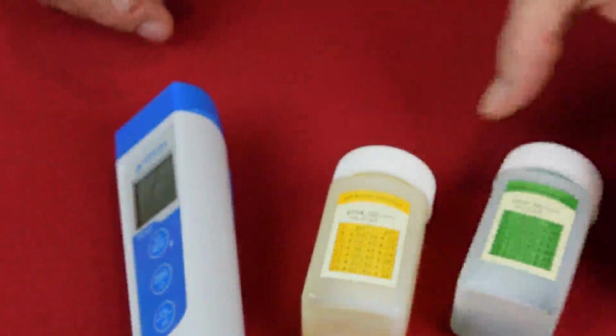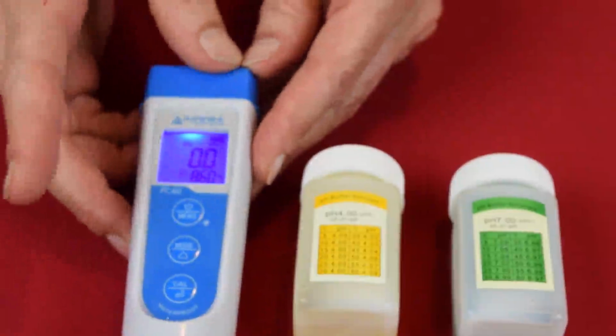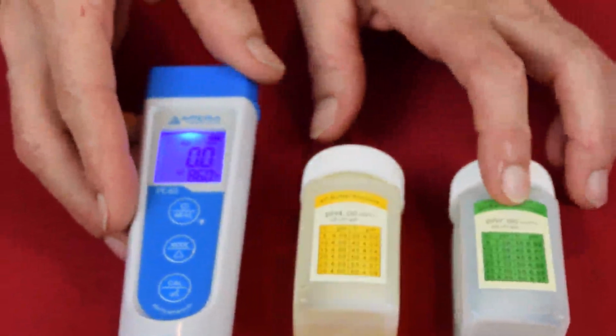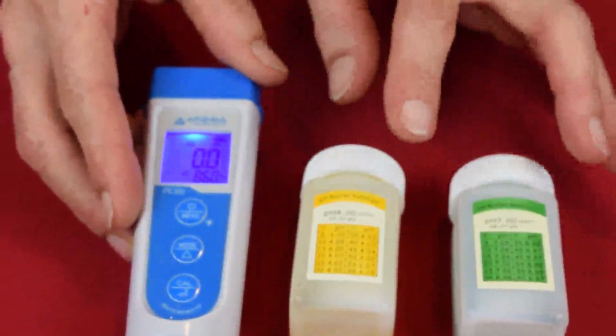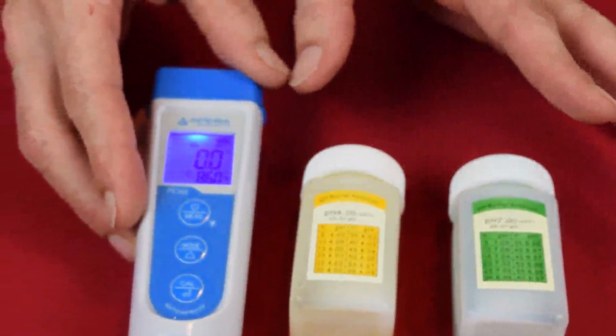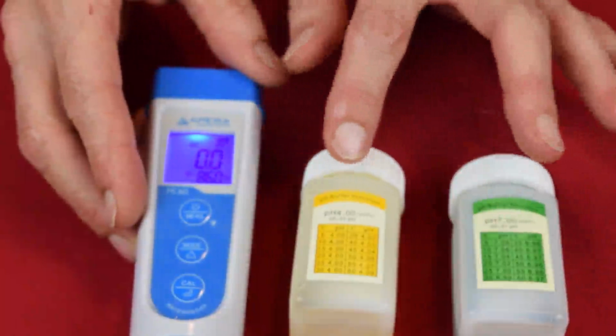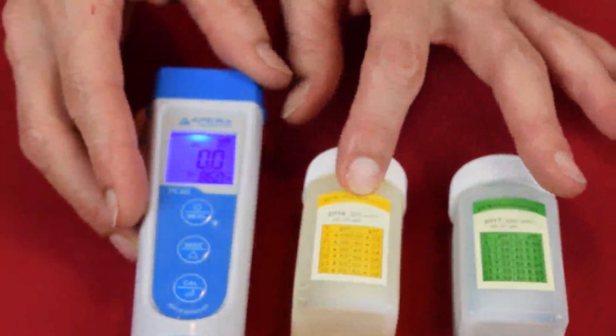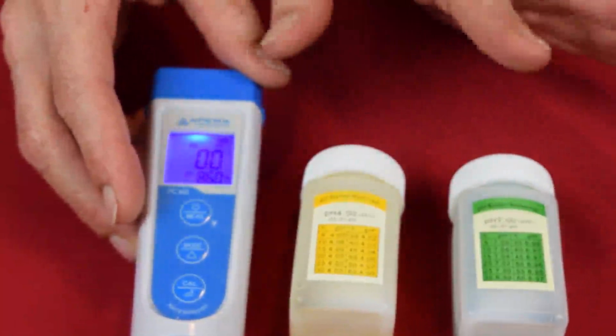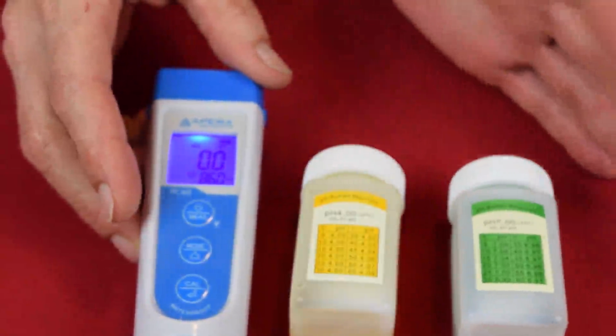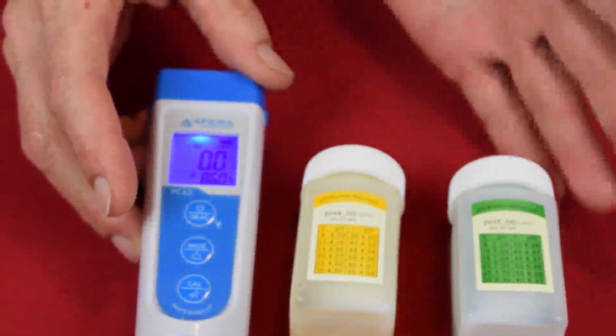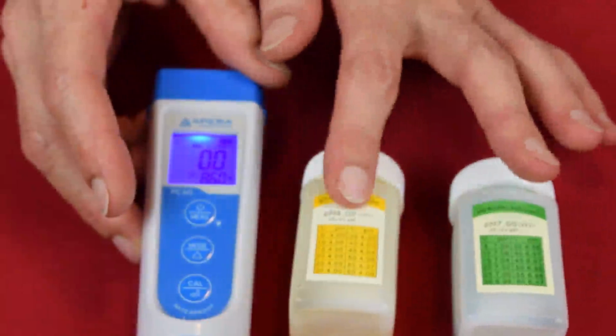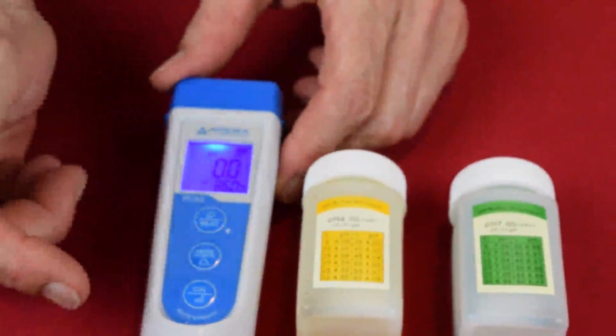Right, so then you want to calibrate this instrument. So you have 2 calibration bottles. You have a pH of 4 and a pH of 7. You can do a single point calibration, which is just with the 7, but if you do 2-point calibration, it'll be a little more accurate. And if you know that mostly what you're going to be testing is on the acid side, then you would use the 4 pH. But if most of what you're testing is on the alkaline side, you can do a 2-point calibration with a 10 pH. This kit only comes with 4 and 7. You have to get the 10 extra if you need that. And for even more accurate results, you can do a 3-point calibration. So you would do the 7, and then the 4, and then the 10. So let me go through the modes now.